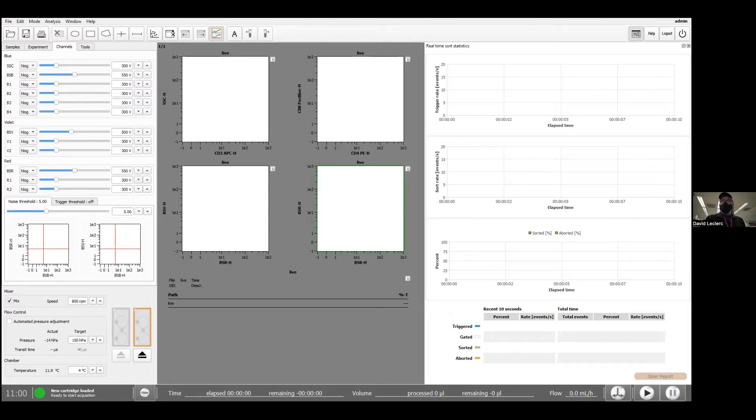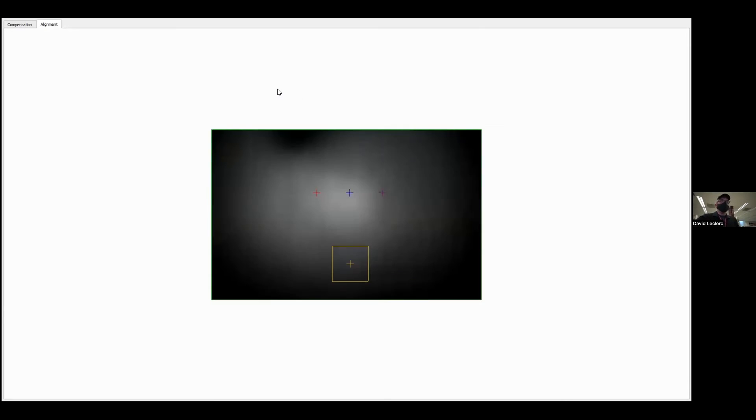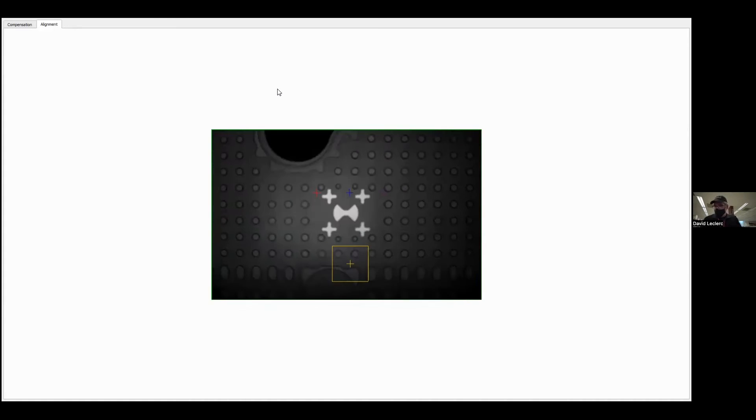I got everything I need to set up my sort, my gates and voltages. So now I'm simply going to press the play button. As I load the cartridge, we see on the secondary screen a camera that basically shoots directly at the chip underneath the cartridge and basically tries to align the camera with the cartridge itself. So basically there's a pattern that the camera will try to find. And when it does, like that's the case now, the cartridge is in alignment in front of the laser beam. The sample starts flowing. And now we see the data showing up on the screen.